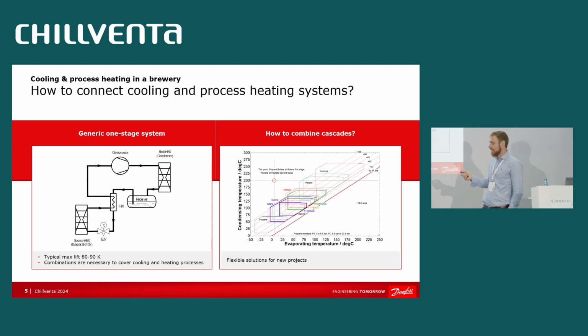But how to combine systems? You do your homework, you map what your sources are, which eventually will result in a certain evaporating temperature, then what your sinks are, which will result in a certain condensing temperature. And then you see where you have an overlap between the envelopes of the refrigerants. You need, I would say, 15, 20 K overlap so the compressor can operate safely in between. Where are we now? We are now up to 130 degrees condensing. This is what we focus on with high readiness in our components and our compressors.